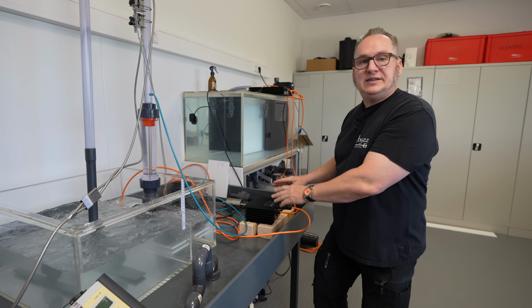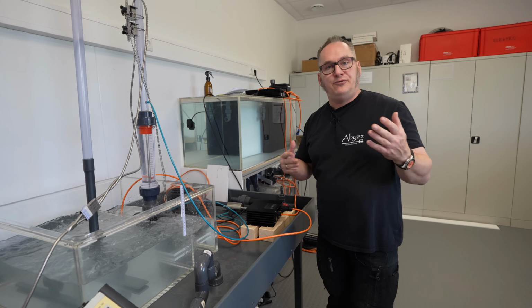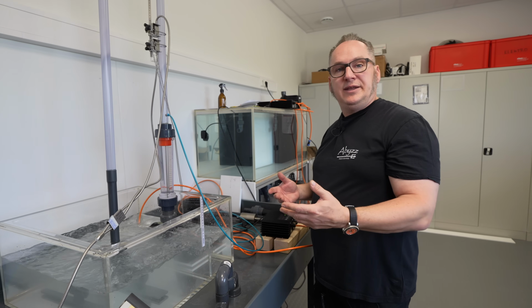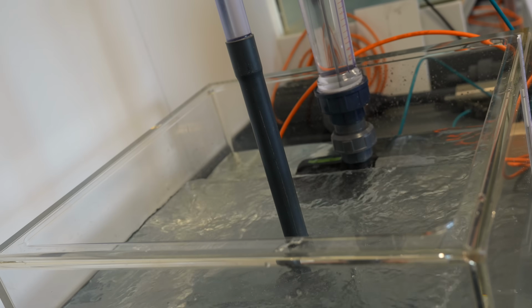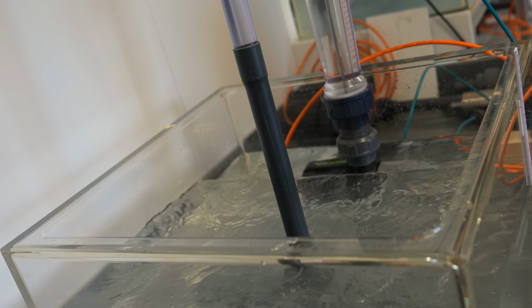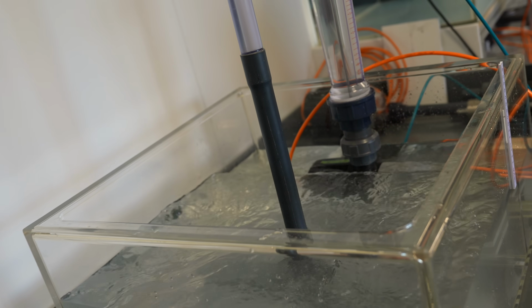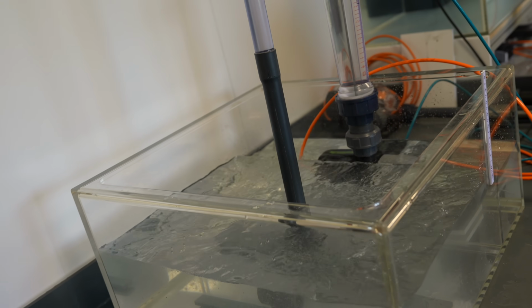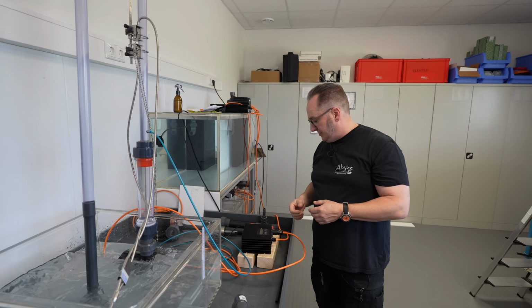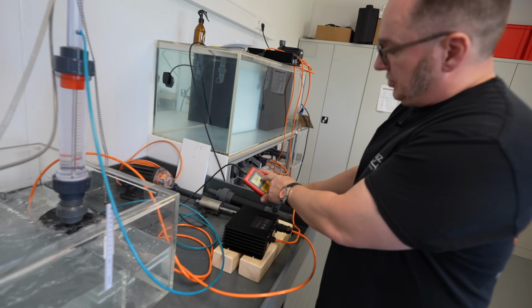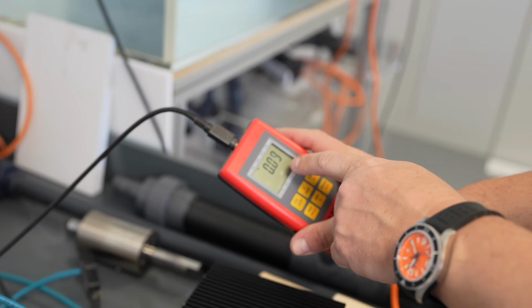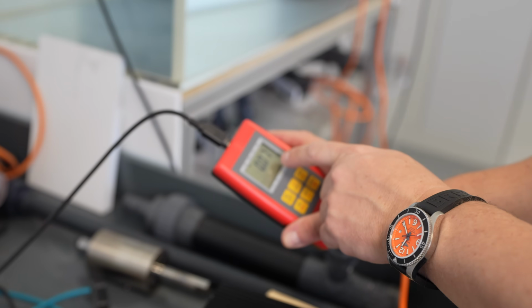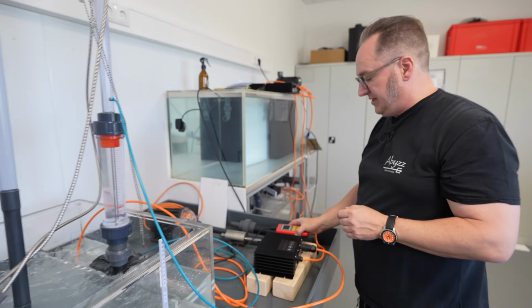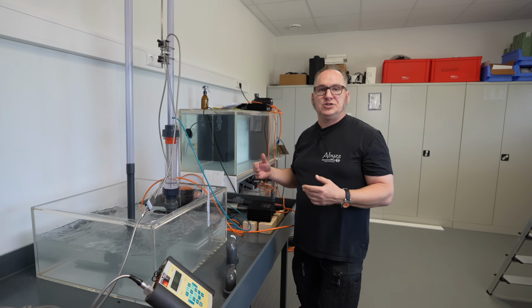So by investing 200 watts instead of 49, we're only getting roughly 60% more flow. That's the big difference in performance for having the right pipe diameter for the turnover that you desire in your system. Also notice that the head pressure is raised from 0.01 to 0.08, 0.07. So we're talking about 6 times the head pressure just by friction of the pipe, and also those 2 soft elbows that we have up there.